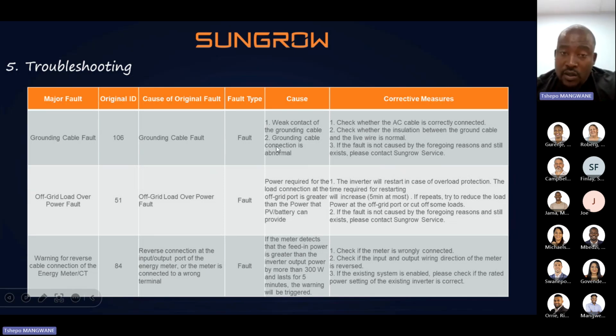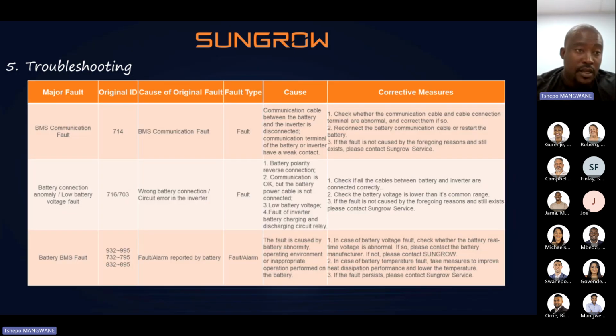Okay. And then if you can't resolve this issue, then you pick up your phone or advise the installers to contact me directly or my other colleagues directly or post on the group, then we attend to the matter. All right. As I've mentioned, these errors are so many, we can't deal with them immediately. So now we have BMS communication fault, which will appear as 714. In this case, if the system does not recognize the communication from the battery side, it won't work. It won't produce anything. It will log into a fault.